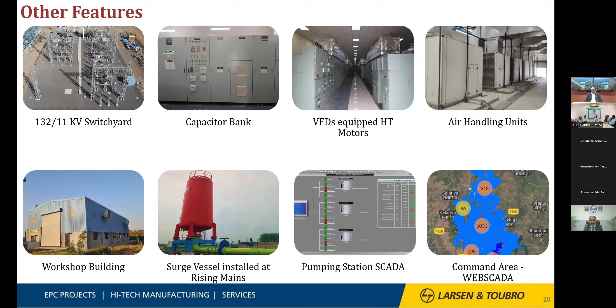because irrigation projects are in remote areas. These projects are not near the city where we have fabrication or repair facilities. So we have kept one workshop building where vendors can come. If any issue comes, they can repair it at the site itself. As we are lifting the water up to a 114-meter height, there is a chance of water hammer also. To arrest that, we have installed surge vessels, which are bladder vessels. Balloon type arrangements are there in them to control the surge. And then the complete system is monitored through the SCADA, and all the command area is developed over Google Map, and it is maintained through the web SCADA.